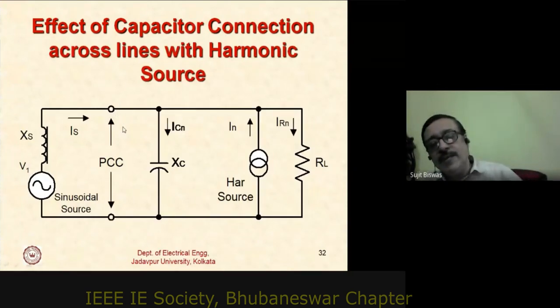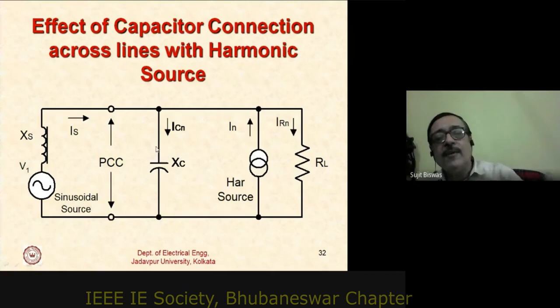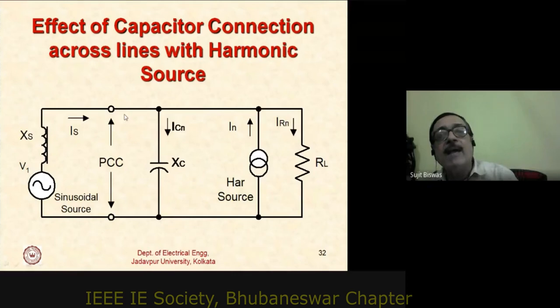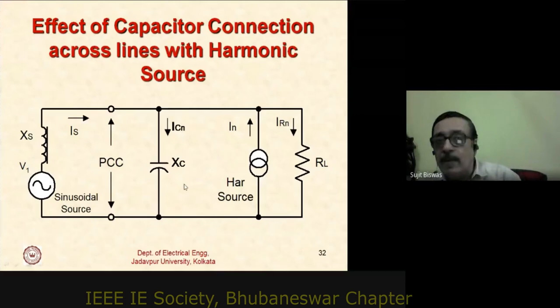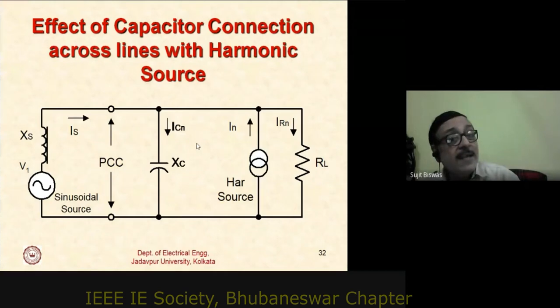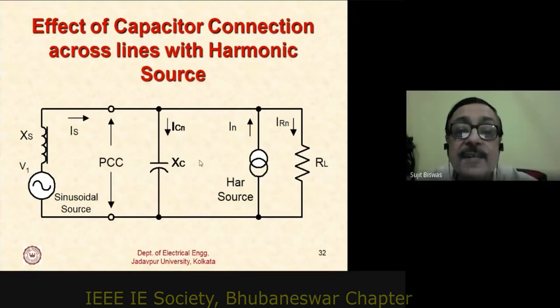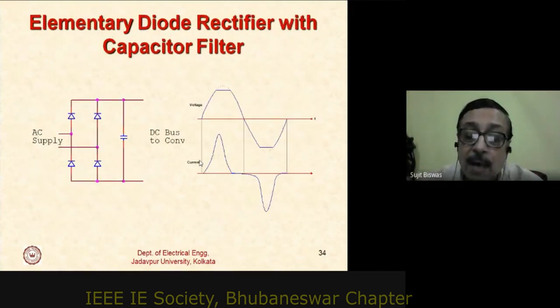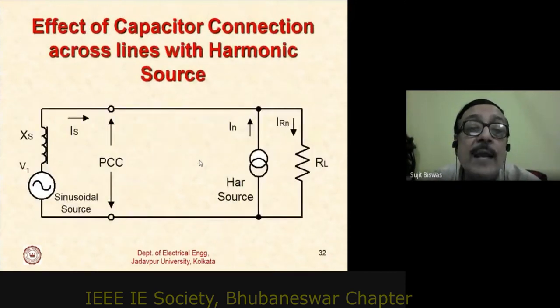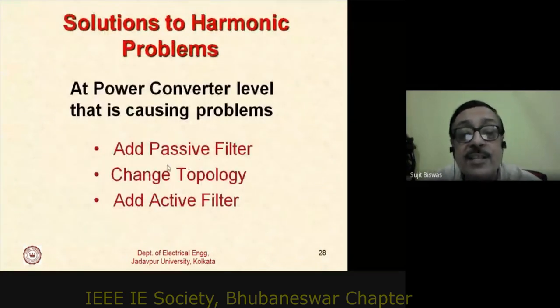The first solution is simply to remove the capacitor — this stops resonances and brings harmonic currents down. This has been confirmed in practice in industry. However, there is still a fundamental displacement angle to correct, and that cannot be done with a simple capacitor — it must be handled through electronic control.